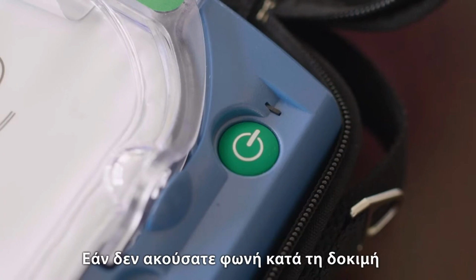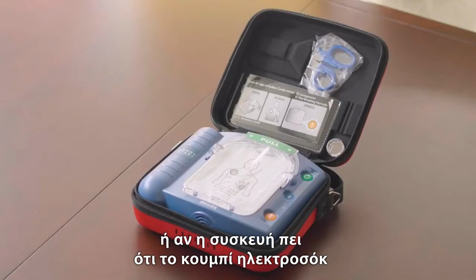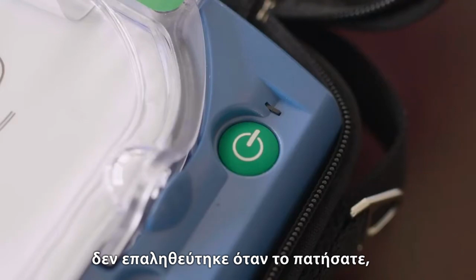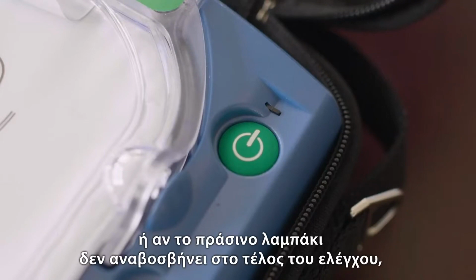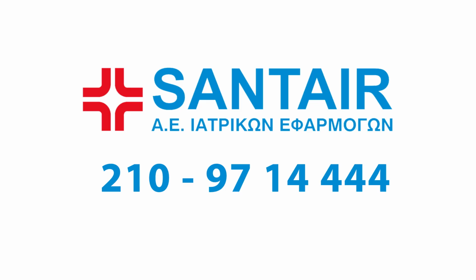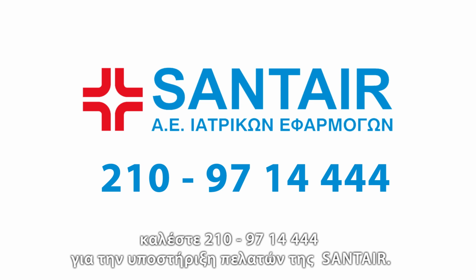After about a minute, the test will conclude, the device will turn off, and the green ready light will start blinking. If you didn't hear a voice during the self-test, or if the device tells you the shock button was not verified when you pressed it, or if the green ready light is not blinking at the end of the test, call 1-866-333-4246 for Philips customer support.